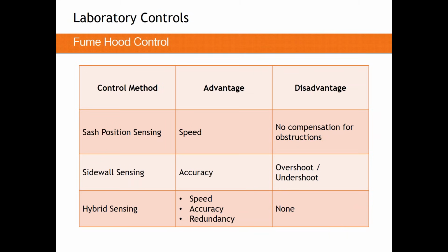So if my sash or sidewall fails, we can still lean on the other sensing element to give us the right, or at least mostly accurate, face velocity on that fume hood, which makes sure we don't ever have to shut the fume hood down for the technology that's sensing that face velocity.